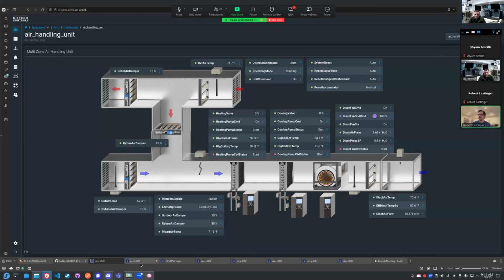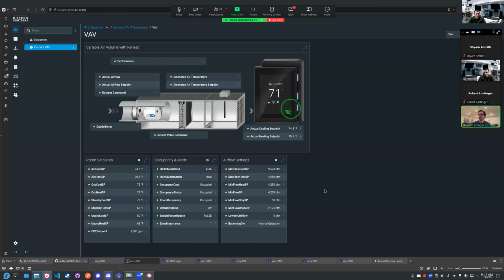Now let's take a look at the VAVs, since I have at least one of them up here. This is the corridor VAV, and if we watch, the airflow shot up way beyond set point. So now the damper is closing, which you'd expect in a real project in a real building.